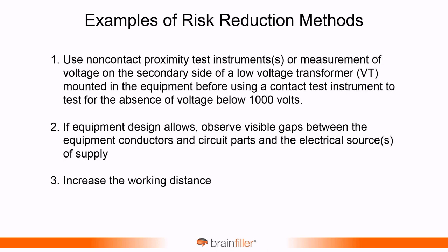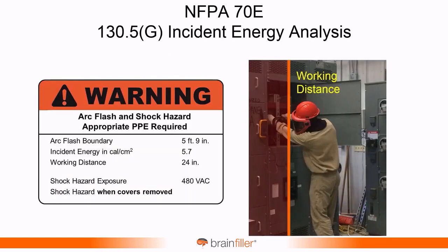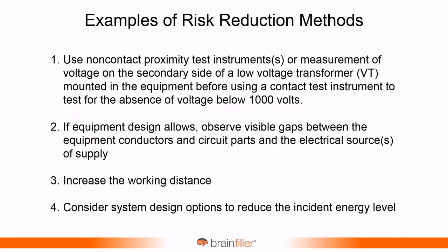Increase the working distance. Now the working distance is really critical for a lot of this, because when someone calculates the incident energy, it's actually based on the distance from the source of the arc flash to the worker's torso and head. And so increasing the working distance, if possible, may go a long way towards helping out. Another example of risk reduction method, consider different design options. Maybe use some type of current limiting type of a device. And remember, I mentioned IEEE 1584. That's going to be coming in, and that's going to give us some options.